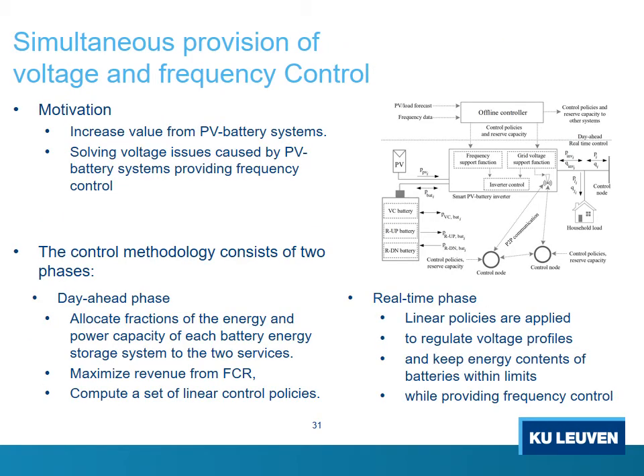When battery energy storage systems are used to provide only one service, such as voltage control, they are inactive or partially used most of the time. Their unused capacity could be used to provide other services, allowing them to generate additional revenues. Hence, there is a need for designing innovative control systems that enable battery energy storage systems to provide multiple services simultaneously, the so-called value stacking. Since frequency control has been identified as one of the highest value services for battery energy storage systems, we are interested in combining distributed voltage control with frequency control.